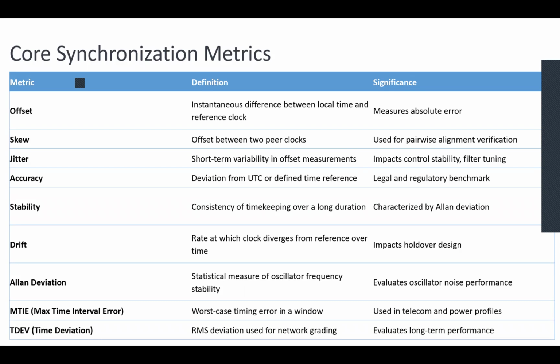Stability is basically defined as the consistency of timekeeping over a long duration. This is one of the parameters that we have to audit to make sure that our time synchronization is passing the criteria, and it is characterized by Allan deviation. Drift, we already talked about, is the rate of the clock's divergence from the reference over time. It normally impacts the holdover design, so you have to pay attention to the drift when you design the holdover state or strategies in your system.